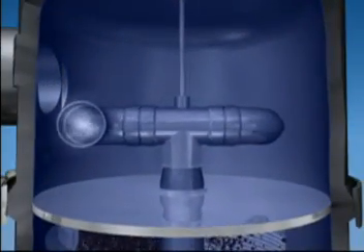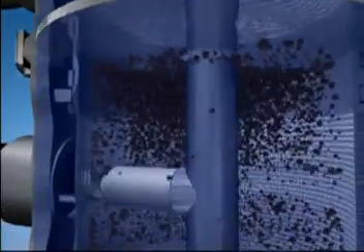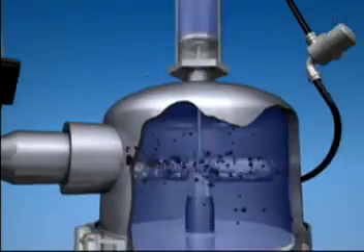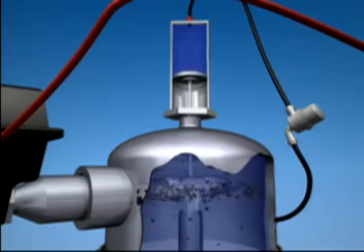The combined linear movement of the dirt collector and axial rotation caused by the electric motor allows the dirt collector to scan the entire surface area of the screen. Particulates are then expelled through the flush valve with the backwash water.